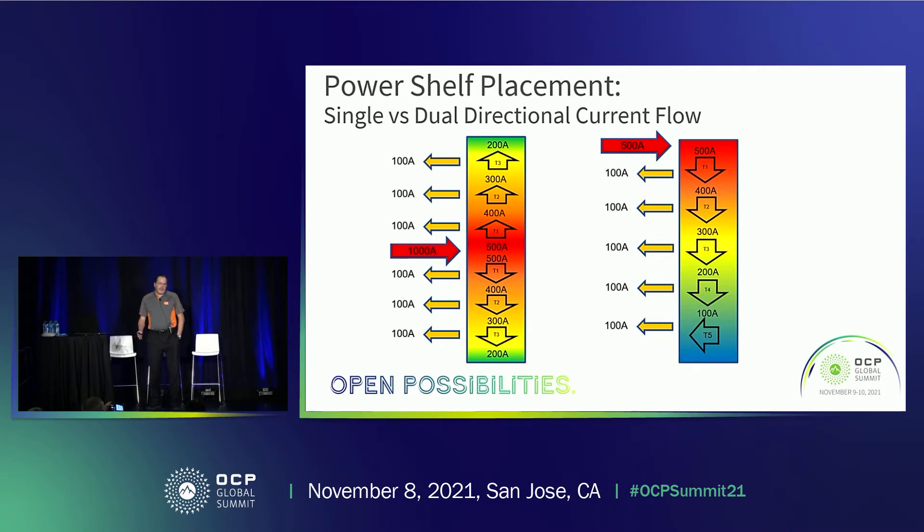The power shelf can now be placed anywhere along the bus bar, but there are effects that need to be considered. If you put the power shelf at the top or the bottom, the capacity of the bus bar is really defined by the total current of the power shelf, so you really have to size the bus bar for that. Now if you place the power shelf in the center, you're actually delivering half the load in either direction. So in this case, the same bus bar rated for 500 amps could be used with twice that current flowing up and down.